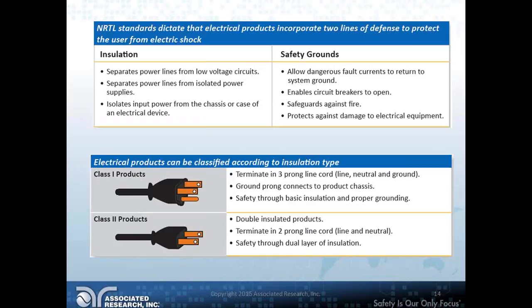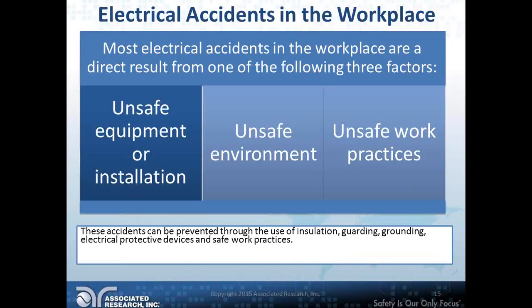And that ties into testing for the next one, because a lot of times when you run a hipot test, you're applying your high voltage to your current carrying conductors - i.e. your line and neutral, the 2 blades - and returning on your ground or chassis. Well, if you don't have a ground or chassis, how do you test? Kind of a sneak peek for next week - I'm not going to get into that now, because I want you guys to attend next month as well.